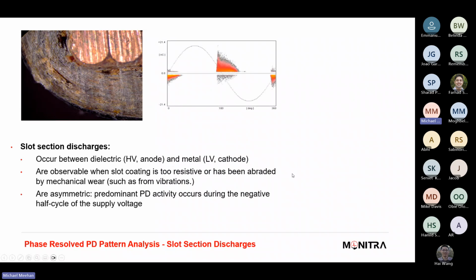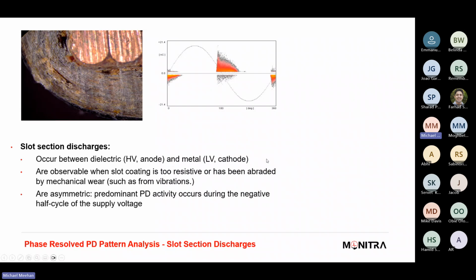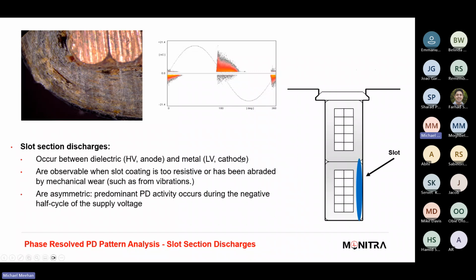So here we've got slot section discharges. So you can see there's a different pattern with the way that these PD occurs. So this is occurring between the HV, which is effectively the anode, and the metal, which is the cathode. So you've got the HV winding, and then you've got your frame. And basically you've got a capacitance between the two, and you can start to get these charge buildups, and that's when you start to get these discharges. And if left, these will again turn into that issue between phase, between insulation, and the machine would fail in time. Again, there's never a definitive time to failure. But what we can say is the probability significantly increases when these types of PD patterns are observed.